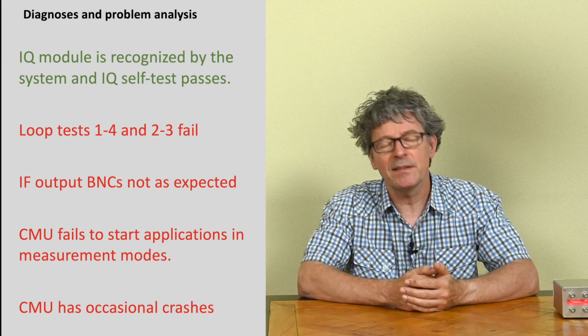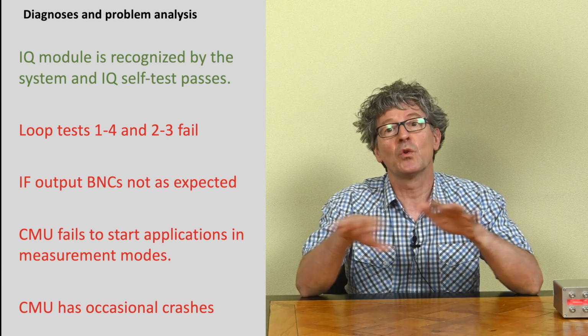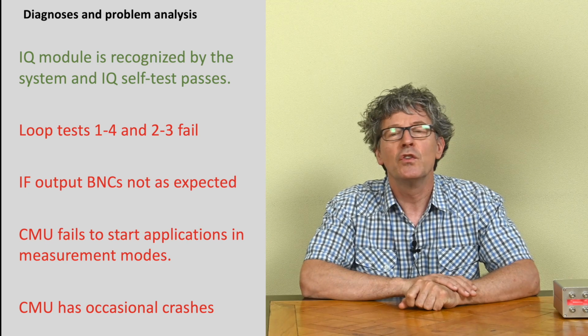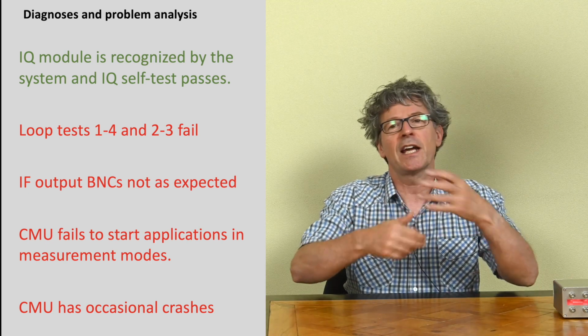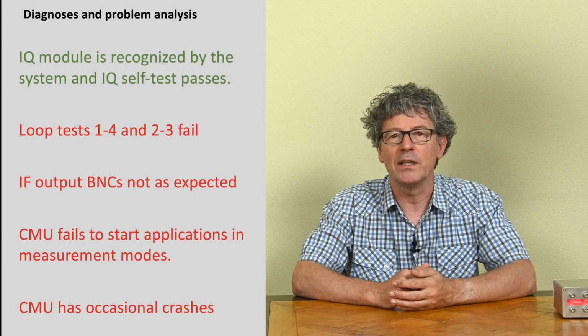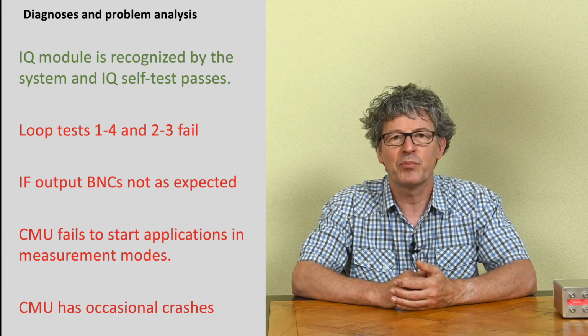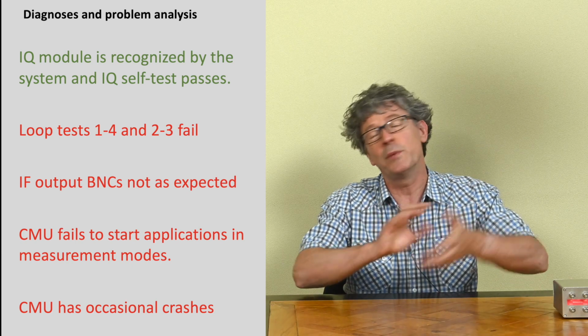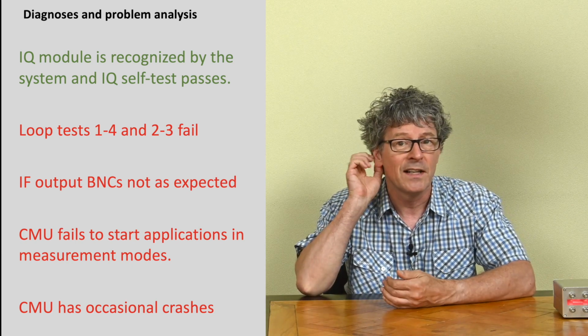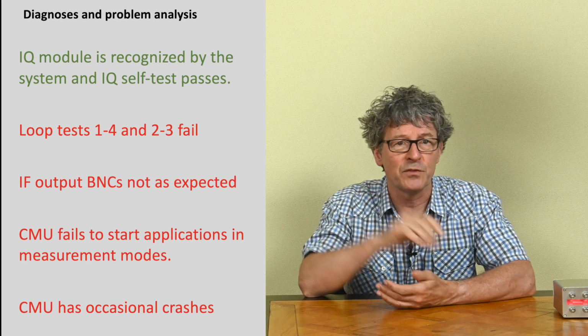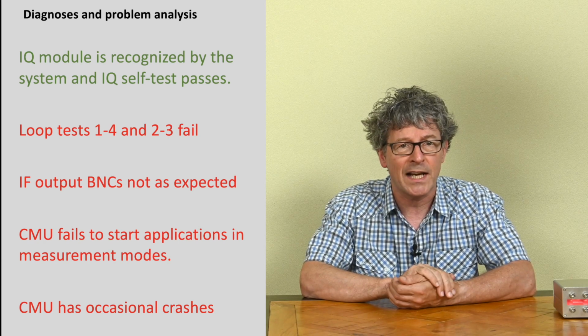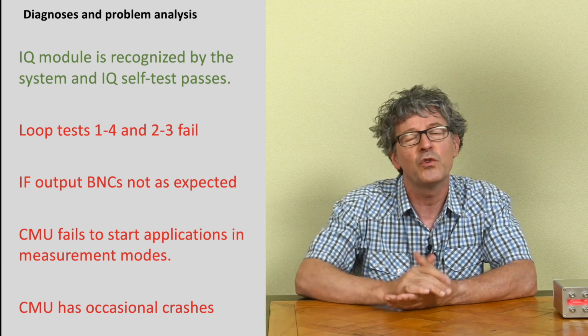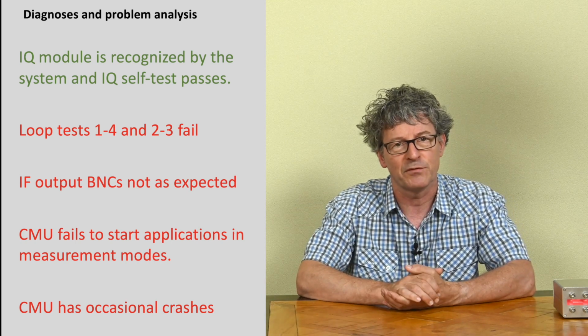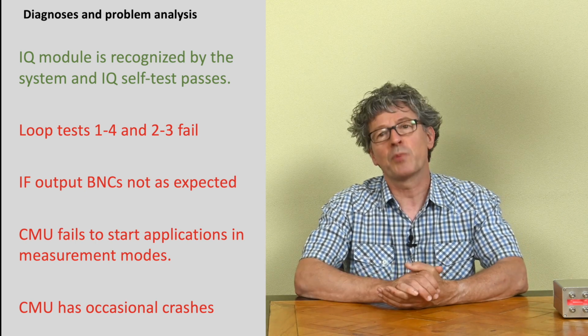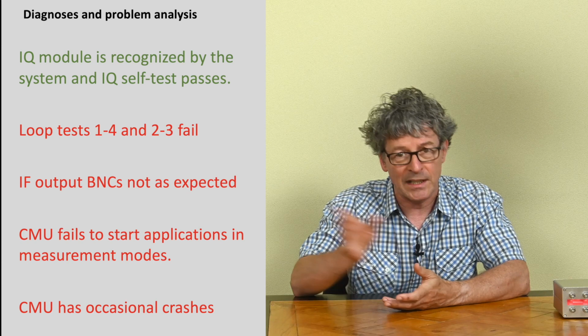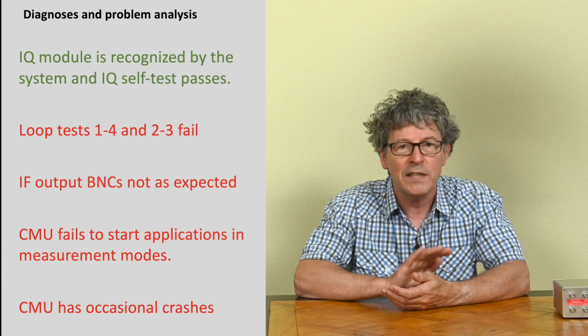What I didn't expect is that, in contrast to all the other advanced units inside, if you go to the system setting page you don't get to see a specific version number or any other information. I have the impression it is a kind of dumb unit that just has switching inside, no more than that. Related to that is the first point of failure. The external loop test from channel 1 to 4 and channel 2 to 3 all fail now on the device if I get it to run. This is not surprising in a way, because my IQ module has not been calibrated into this device, but I don't know where to calibrate it.